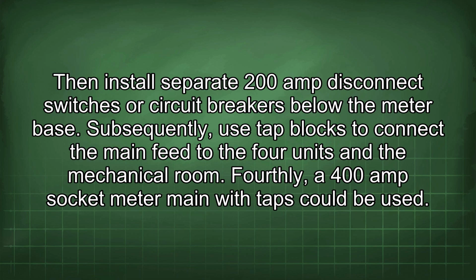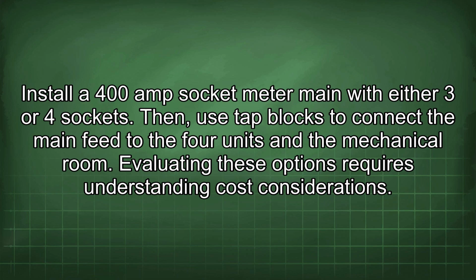Fourthly, a 400 amp socket meter main with taps could be used. Install a 400 amp socket meter main with either 3 or 4 sockets. Then, use tap blocks to connect the main feed to the 4 units and the mechanical room.